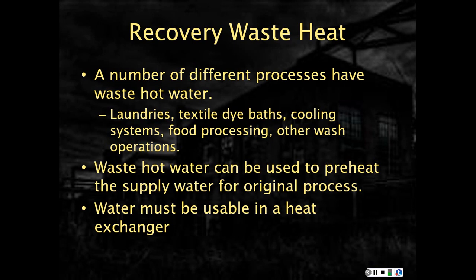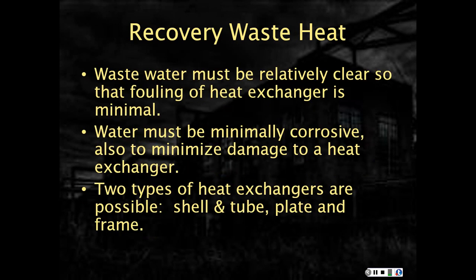The water must be usable in a heat exchanger. So the wastewater must be relatively clear so that fouling of the heat exchanger is minimal. Otherwise, you end up with so much service that it doesn't really pay for itself, whatever energy you're saving by extracting it out of the water. The water also must be minimally corrosive, also to minimize the damage to the heat exchanger.